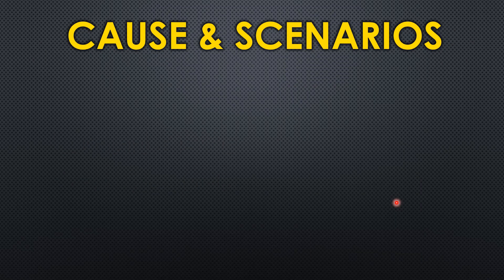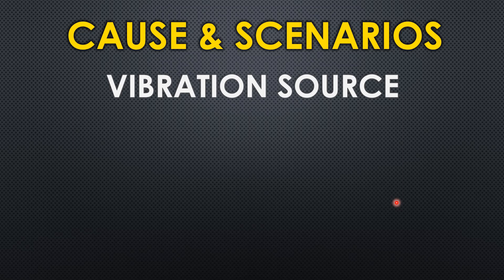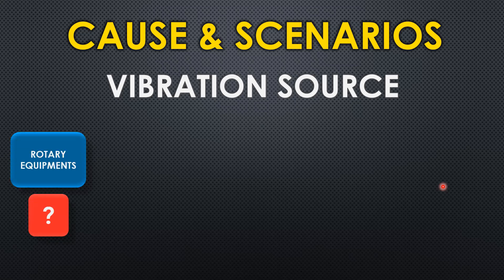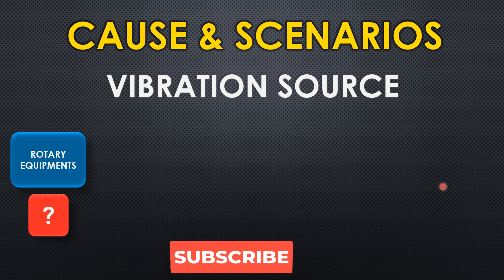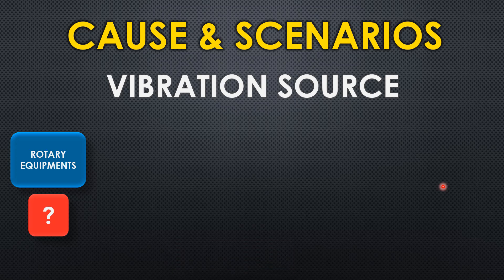Now let's go to the causes and scenarios. First, we need to identify the vibration source. The first source is rotary equipment — pumps, compressors, and turbines. Rotary equipment generally generates vibration because of the rotor within the equipment, and this vibration slowly gets transferred to the piping system. If the piping is not supported to handle this vibration, there will definitely be failure and damage in the piping.